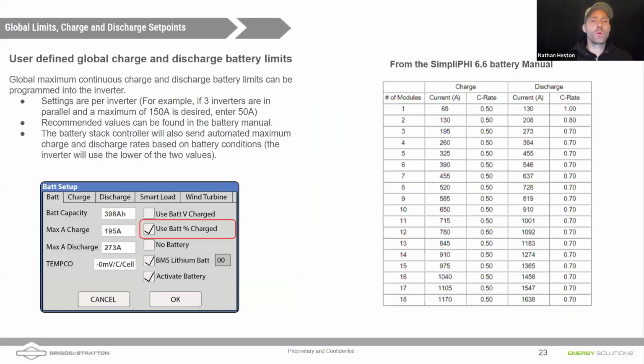Well, let's suppose for some reason, maybe the communications on the battery get disrupted, whether maybe a cable gets unplugged or something happens. It will default to the user-defined parameter. So it's a good idea to go through and manually program the Sol-Ark as well. The other thing to point out is that the Sol-Ark will use the lower of the two numbers. So if I set a global charge limit of 100 amps, even though the battery is capable of taking 195 amps, it will use the lower of the two numbers.